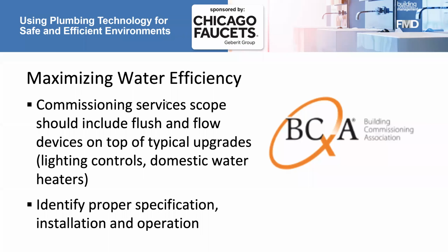Too often with these renovations, there may be no initial complaints, so everything is okay to go from a day one perspective. But if you have a performance-based strategy, or as you get into excessive usage with these systems, you can find errors on day two that you're left having to deal with instead of having the construction and design team deal with them. Include flushing efficiency, flow rates, and set points in your automatic systems.